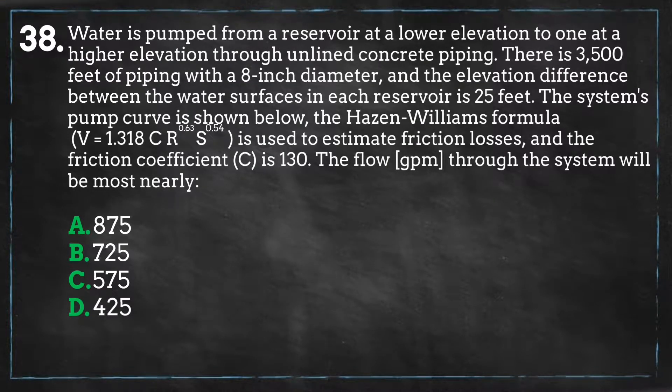So we have the Hazen-Williams equation, where V equals the flow velocity through the system, C equals the pipe roughness coefficient, R equals the hydraulic radius, and S equals the slope of the energy line, or the head loss per length of pipe. Since we are using US customary units, the coefficient will be 1.318, and when using SI units, the coefficient will equal 0.849.